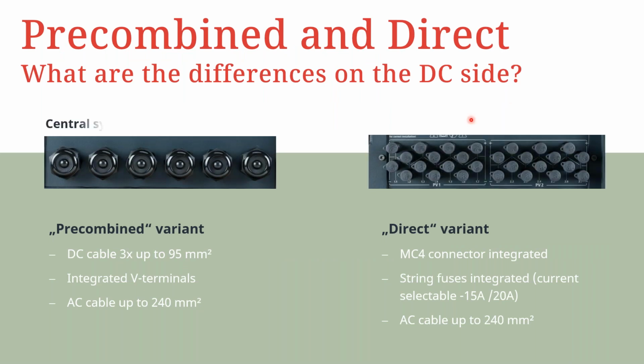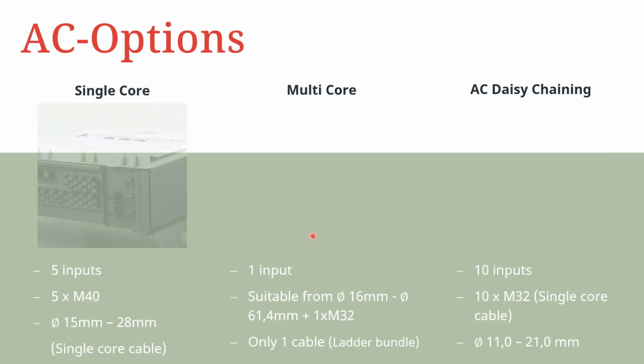If you look at the 2 versions of the Tauro inverters, the pre-combined and the direct version, the backside or the DC area especially can tell you which version you're working with. For the pre-combined, you have the 9 or the 6 cable glands that are integrated, and for AC power, you can connect up to 240 millimeter square. For the decentralized design or the direct variant, we have MC4 plugs provided for connection. Then for the string fuses, you have a choice of either 15 amps or 20 amps integrated within the inverter. For AC, we still have the same cross-section of up to 240 millimeter square.